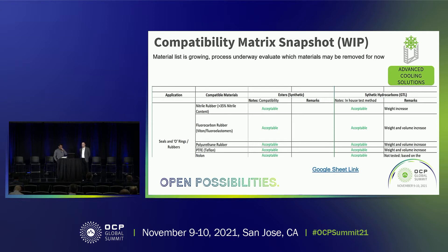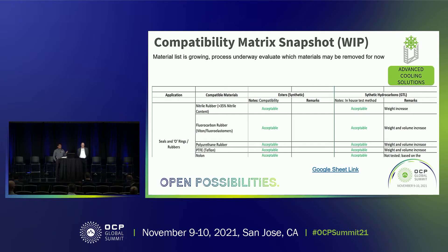Thank you, John. Good morning, everyone. So this slide — as part of the committee, we actually asked every fluid supplier in the market to come forward and do some material compatibility testing for different IT components. This is just a snapshot, but there is a list of more than 100 different types of IT components being tested by each of these individual players, involving synthetic esters, natural esters, synthetic hydrocarbon, GTL, and also two-phase fluids. All these manufacturers have contributed to this spreadsheet.